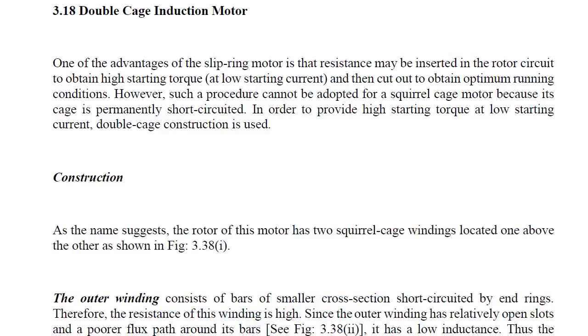First, we will discuss the double cage induction motor. One advantage of the slip ring motor is that resistance may be inserted in the rotor circuit to obtain high starting torque with low starting current, and then cut out to obtain optimum running conditions. In the slip ring type induction motor, we can connect external rotor resistance in the rotor circuit to improve the starting torque, since torque is directly proportional to E2·I2·cos(φ2). By adding rotor resistance, we improve the power factor, and due to this increase in power factor, the starting torque is improved.